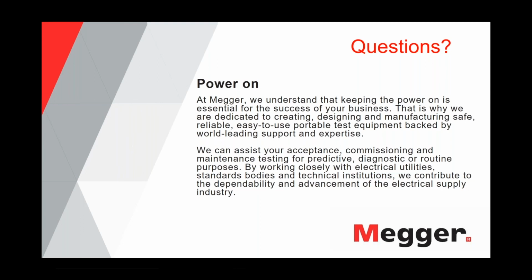And sometimes even seasonal things have to be taken into account. We had customers, they had problems in spring, and then they repeated the measurement and they got different results in summer because they had a cable or an asset in an extreme environment that was very weather sensitive. And again, important feeder cables naturally more often because it would be a much higher impact to lose those cables. So it really depends on the results and on the asset overall.